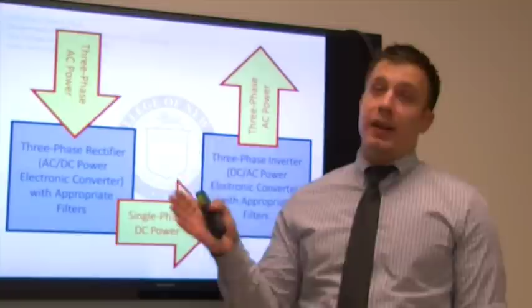It converts the three-phase AC power supplied by network A to single-phase DC at a higher voltage. This power may be transmitted over longer distances with greater efficiency as compared to the lower voltage AC. And at the other end of the HVDC line, a power electronic inverter converts the single-phase DC to three-phase AC. This power is then supplied to network B, or the other network. These power electronic devices use high-frequency switching to manipulate voltage levels as well as shape the voltage and current wave.